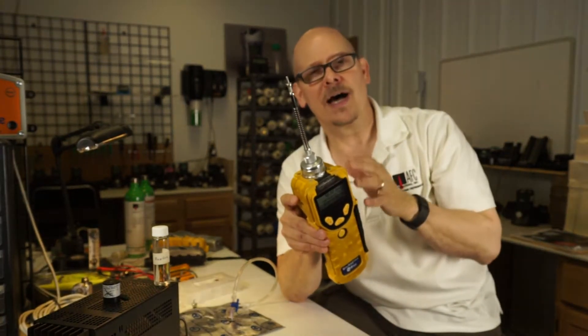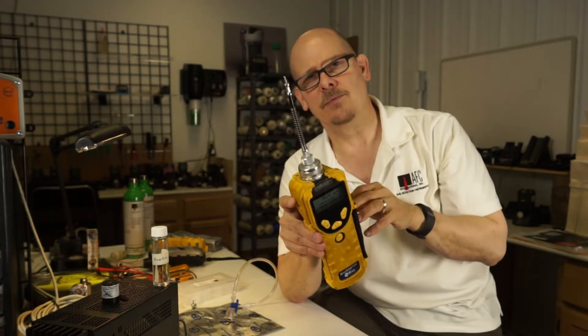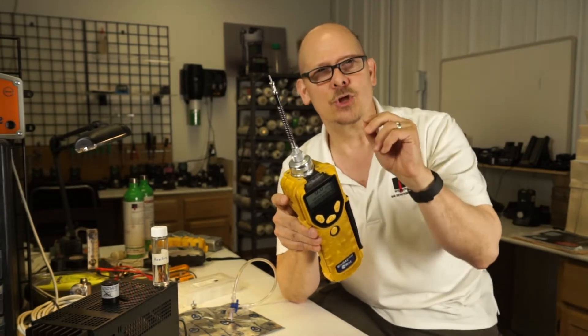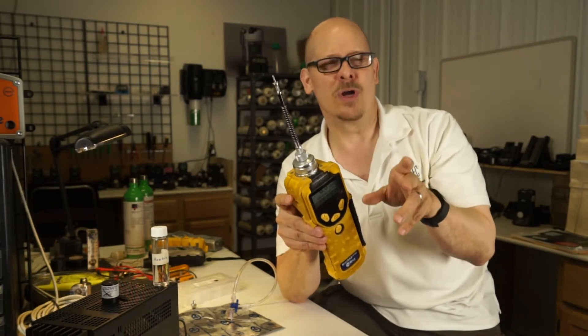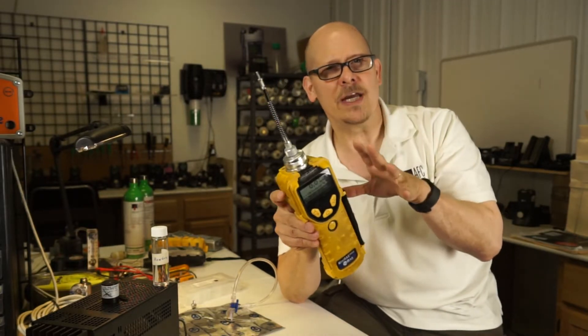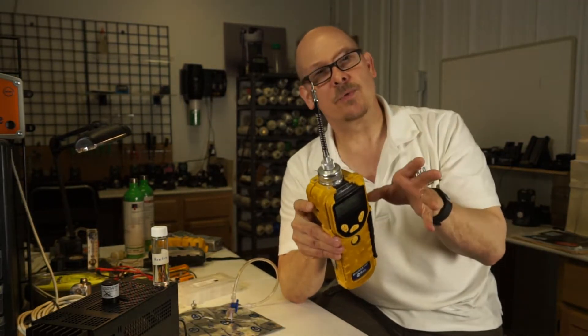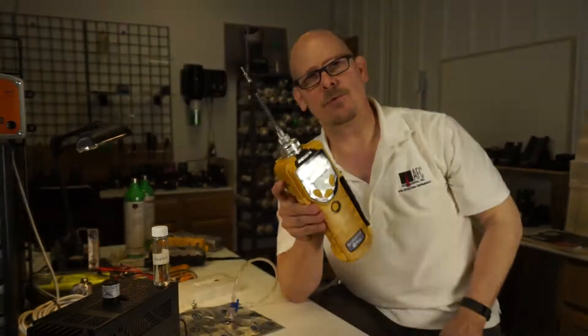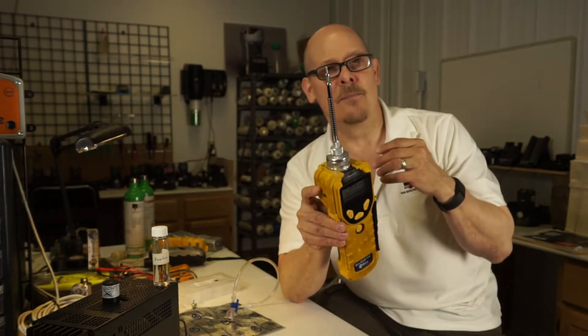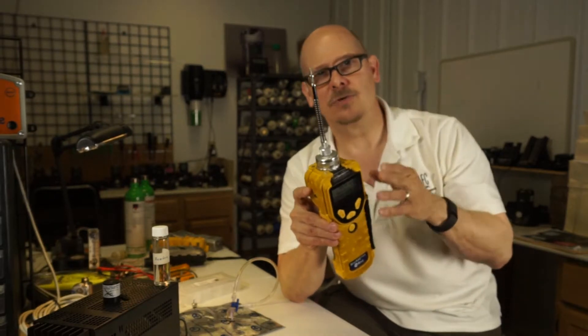We have a very good high range capability with the MiniRAE 3000. We can get up to 50,000 parts per million, yet look at low concentrations at 0.1 ppm levels. So the huge range, quick response, and quick recovery make the MiniRAE 3000 very invaluable for hazmat operations, or even a meth lab investigation, or even for arson.